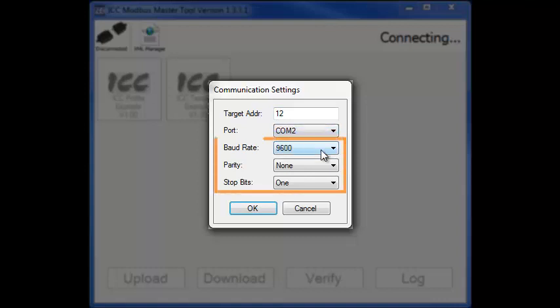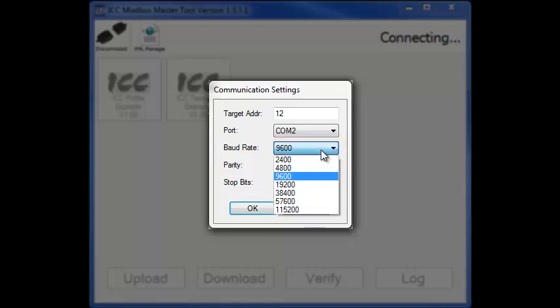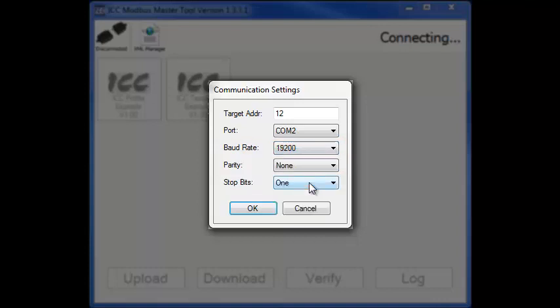The final three settings must match the settings on your Modbus slave. This can be found in the documentation for your device or in the configuration parameters on the device. Select the baud rate from this dropdown to match the baud rate of your slave device, and do the same with the parity.